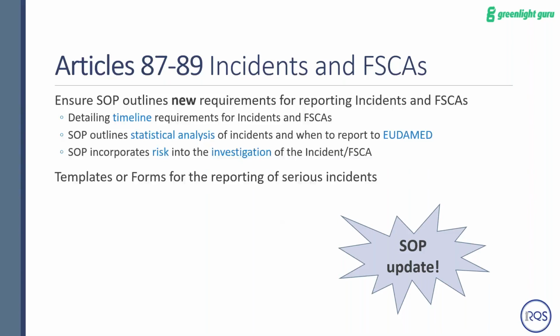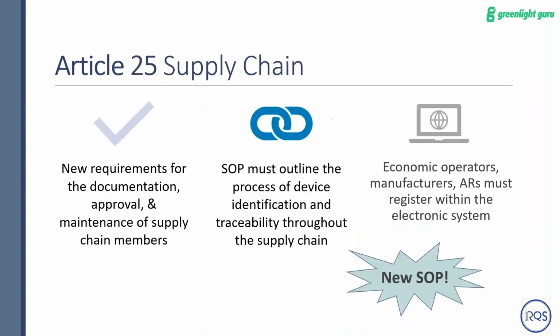Make sure your SOP outlines the statistical analysis of these two, and that you incorporate risk into the investigation of these, and that it's a continual loop of, you get incidents or reports back, and you're able to incorporate that into your risk of your device. Templates or forms should be created if they haven't already been, and make sure they're compliant with the latest version in MDR.